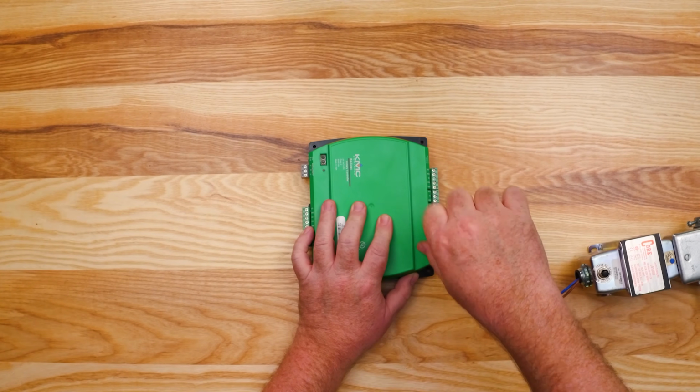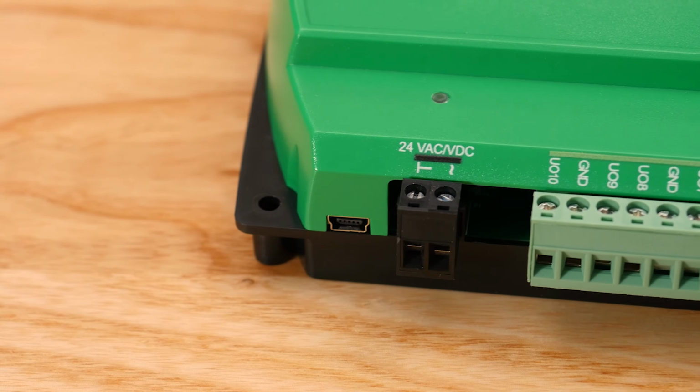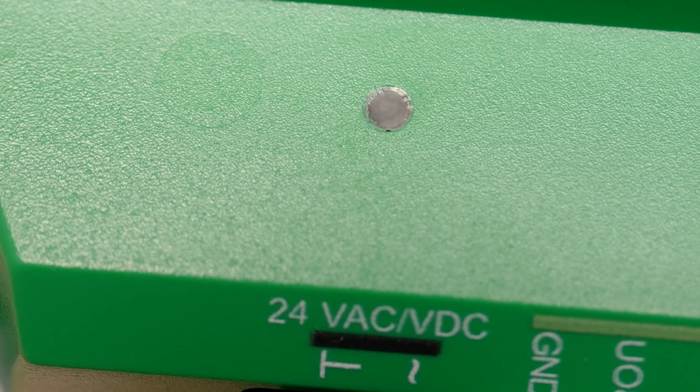When wiring, note the polarity of the controller's terminals. The common terminal is represented by a T-shape and the phase terminal is shown by a wavy line. This can be important. If wired incorrectly, the controller could be damaged and need replaced. When powered correctly, a green light will turn on and begin flashing. And that's how you wire the outputs, room sensors, and power for a KMC Conquest BAC-9300 series controller.